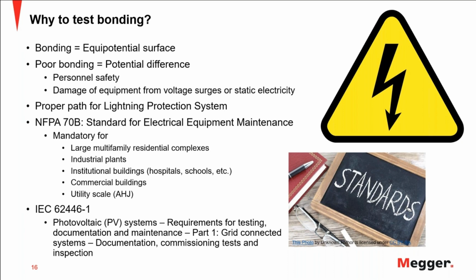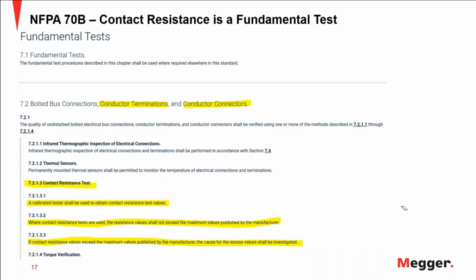If we look at IEC 62446-1, this is the standard with the requirements for testing, documenting, and maintaining photovoltaic systems. They also mention that this is a test that shall be performed. These are a couple of slides I have showing screenshots of these documents that I'm mentioning. So from NFPA 70B, contact resistance is one of the fundamental tests. It tells you that you should use a calibrated instrument to obtain contact resistance test values. So this is not telling you to do a continuity test or a verification. You want to get the actual contact resistance values.